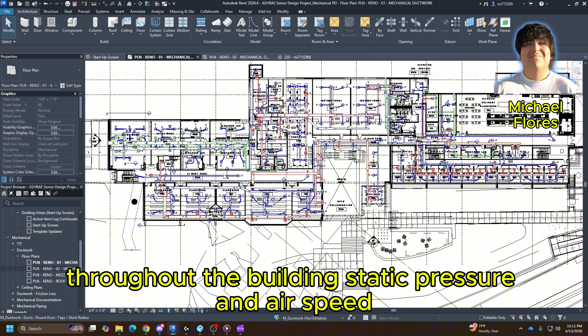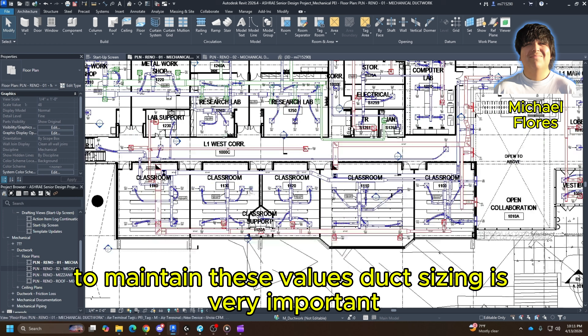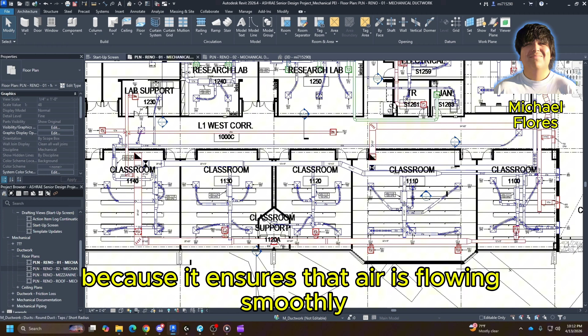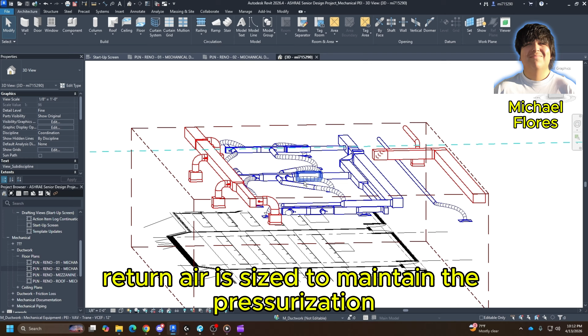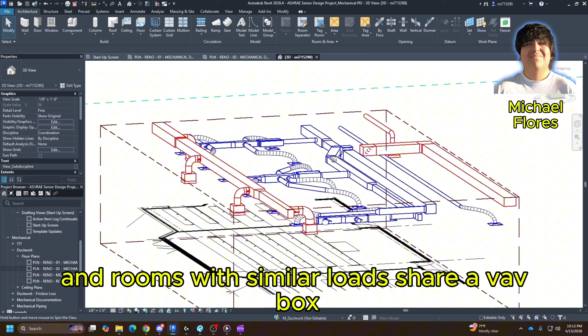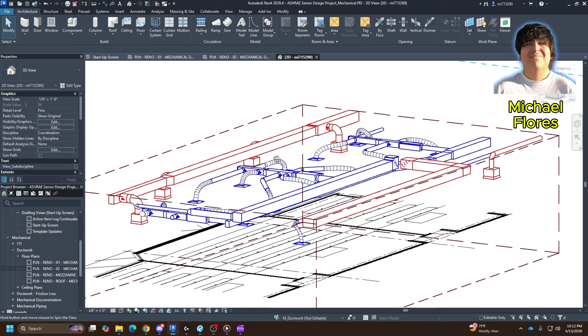Autodesk Revit was used to design the duct throughout the building. Static pressure and airspeed in feet per minute were considered. Size reductions were made following a diffuser to maintain these values. Duct sizing is very important because it ensures that air is flowing smoothly, which leads to energy savings. Return air is sized to maintain the pressurization in these rooms, and rooms with similar loads share a VAV box. The thermostat is then placed in the room with the highest load to control the air.